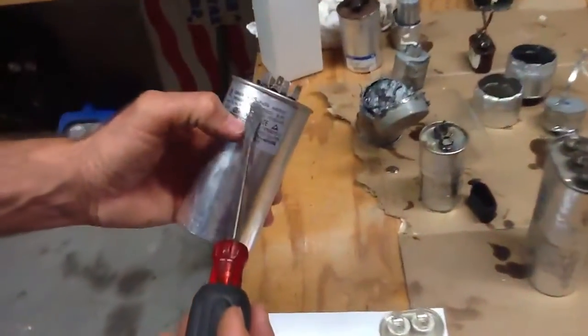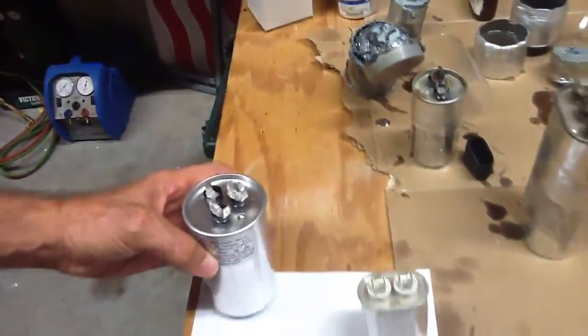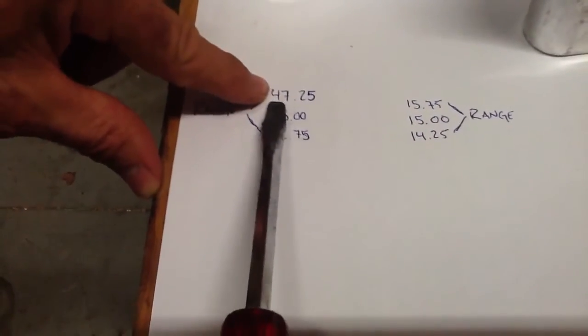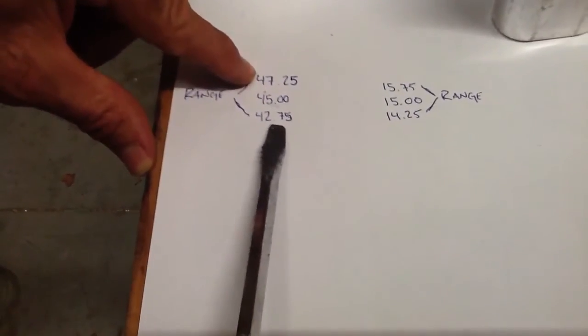So let's talk about this — 45 microfarads plus or minus 5%. What that means is you can go as high as 47.25 or as low as 42.75.